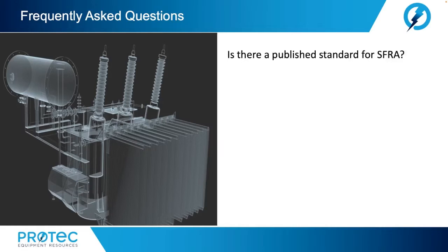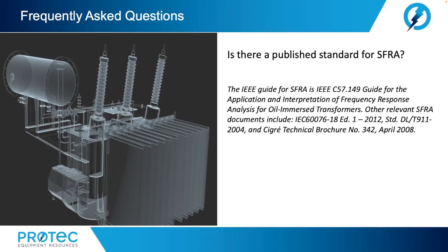Now, let's address some frequently asked questions. Is there a published standard for SFRA? The IEEE guide for SFRA is IEEE C57.149, Guide for the Application and Interpretation of Frequency Response Analysis for Oil-Immersed Transformers.